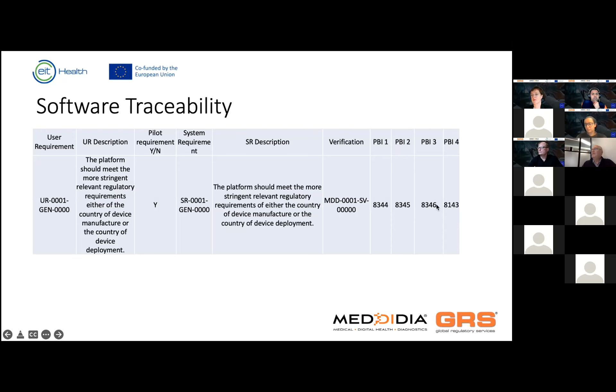has been translated into, and a unique verification and validation number. So when you verify that software, it's part of the verification script. And here in columns sort of 6, 7, and 8 is which PBI that was built into and what the unique identifier is, so that when you're audited, either through your technical file or during your 13485 audit, you can demonstrate how that requirement was met.